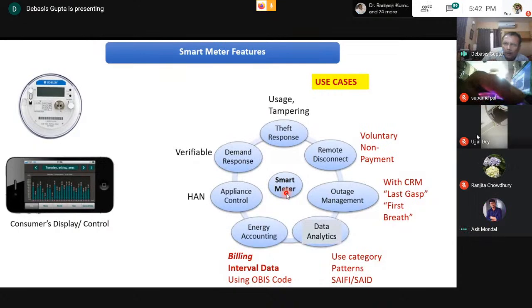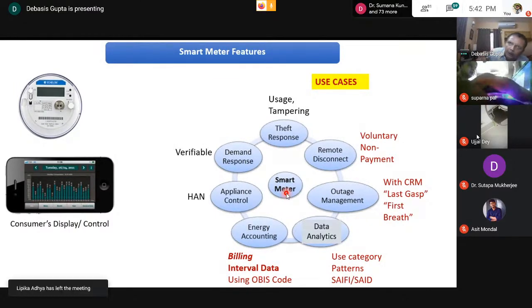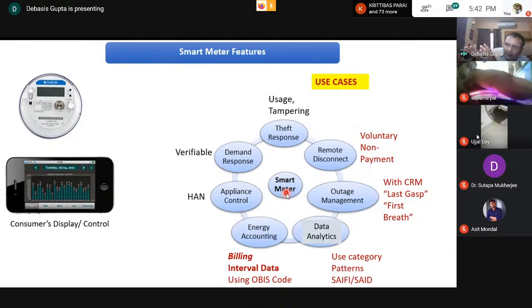By looking at the number of meters which have gone out and their geographical dispersion, we can make out whether it's a cutoff fuse, an upstream pillar box fuse, an RMU that is tripped, or a circuit breaker in the substation. Your SCADA system and ADMS system, using this last gasp data, will be able to guide the crew management system to go to the right place.